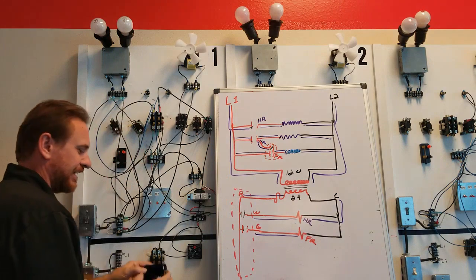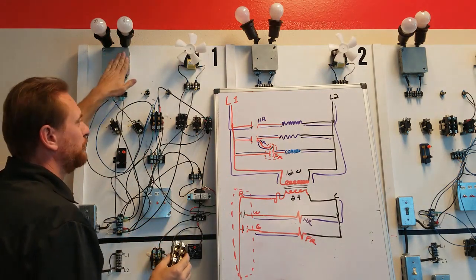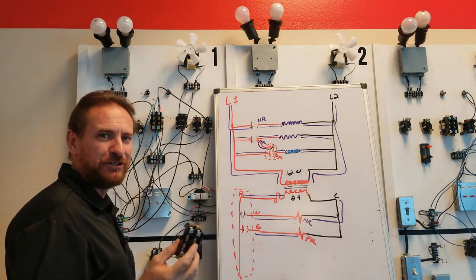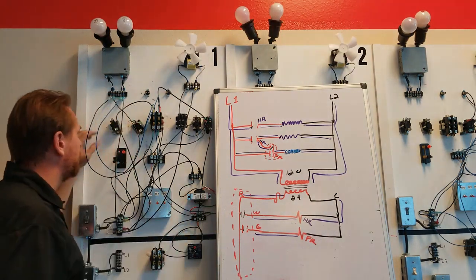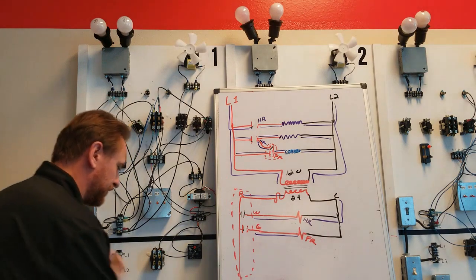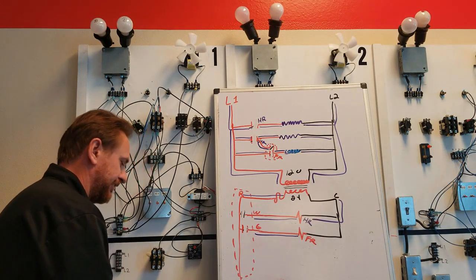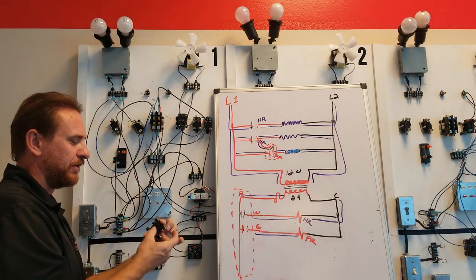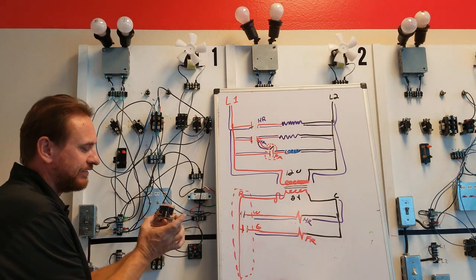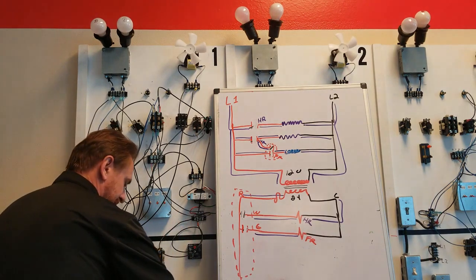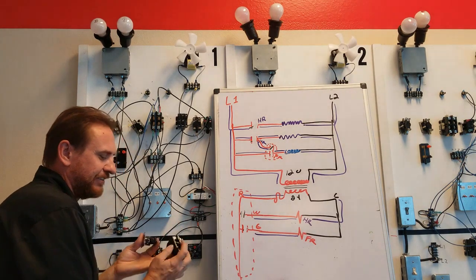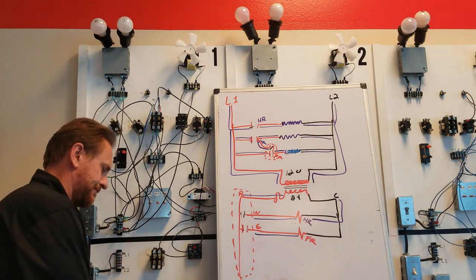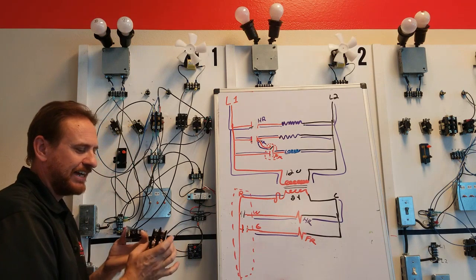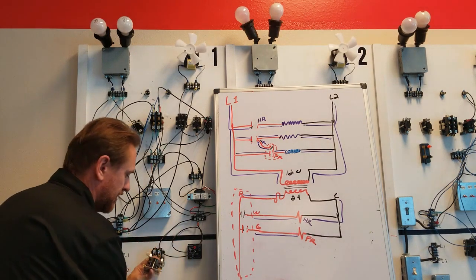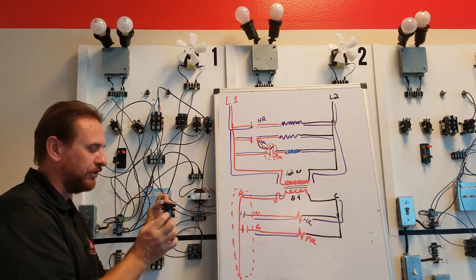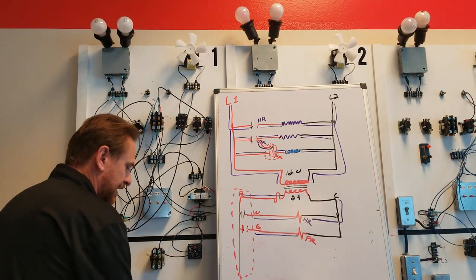I can use a contactor. I have 2 switches, I have 2 loads. But this is not the only thing that we use to control heat. Some manufacturers use what we call a sequencer. A sequencer is a thermal time delay relay. So this is a sequencer right here, or a thermal time delay relay. This is going to be the low voltage. So on my contactor, these very side parts are my low voltage. The sequencer, these very bottom ones, are my low voltage, and they are golden in color. Here I have 2 switches.